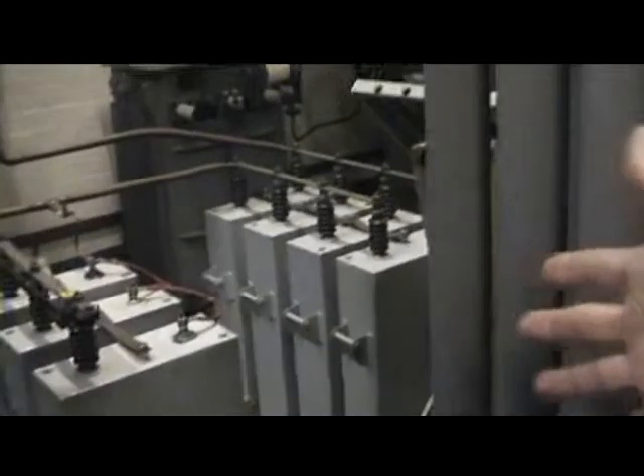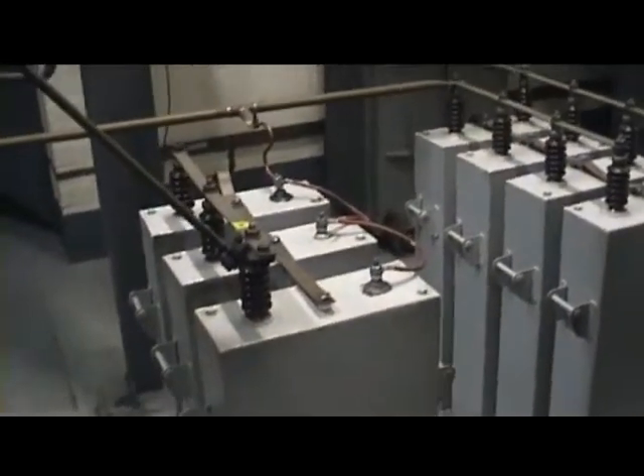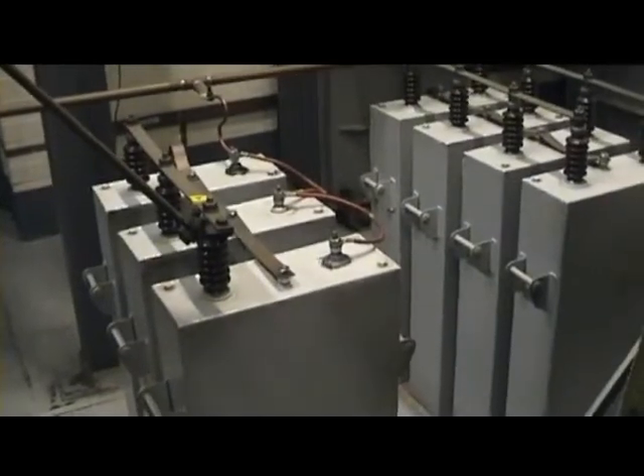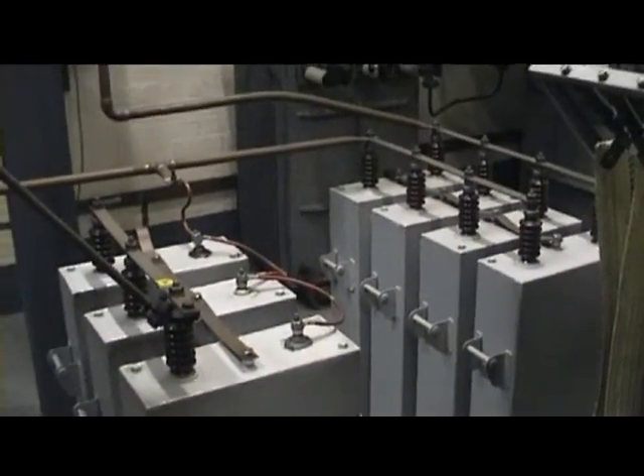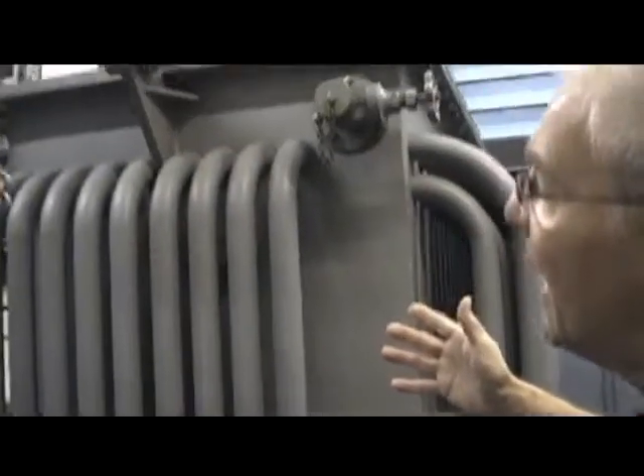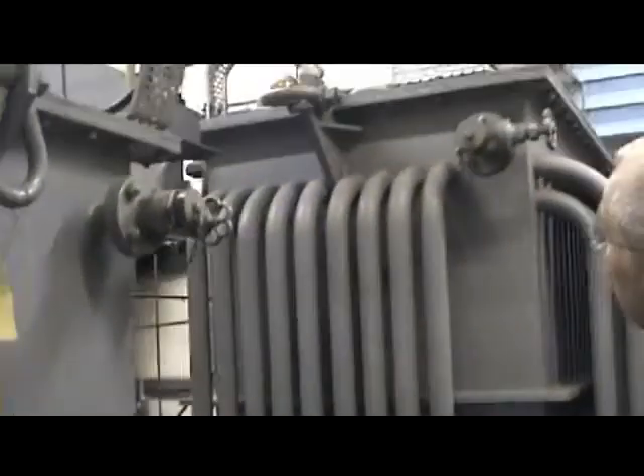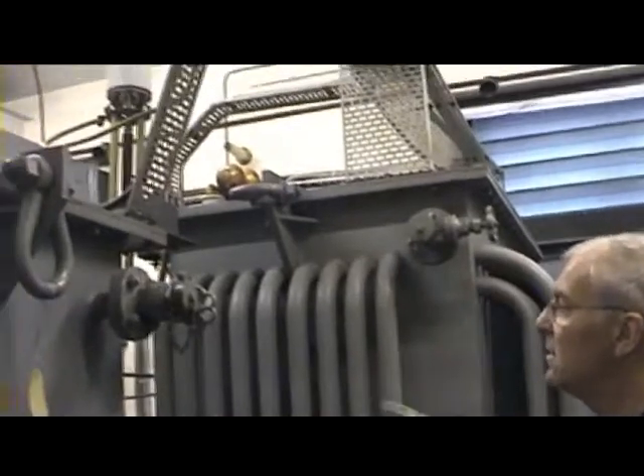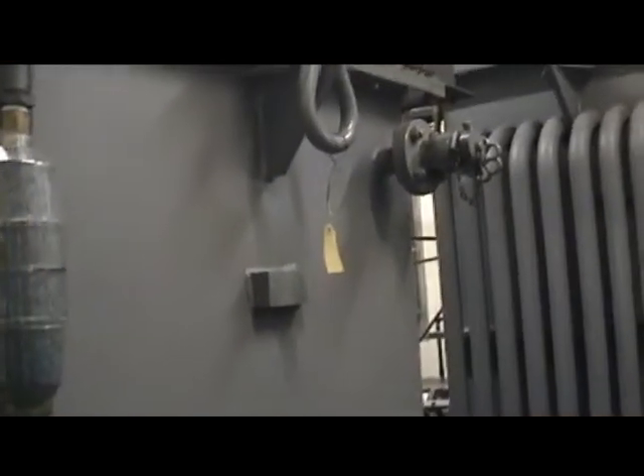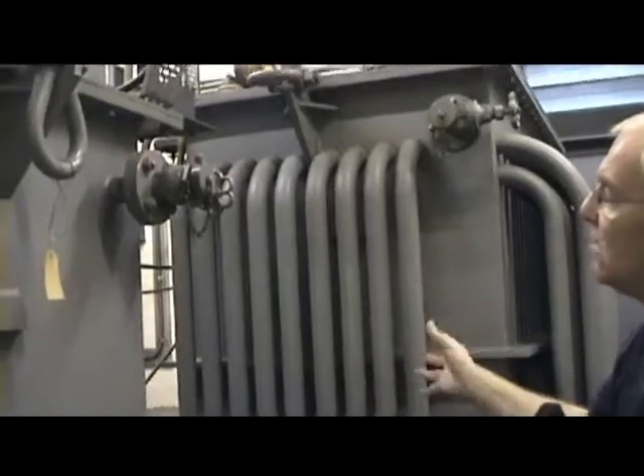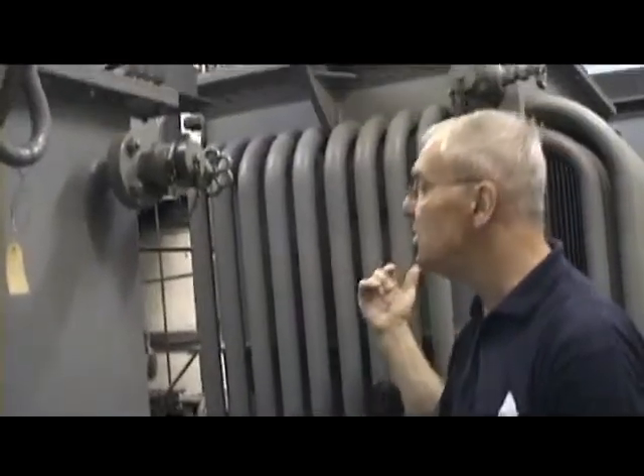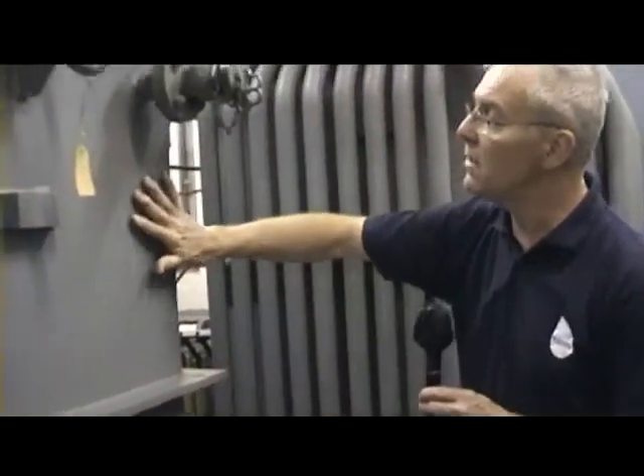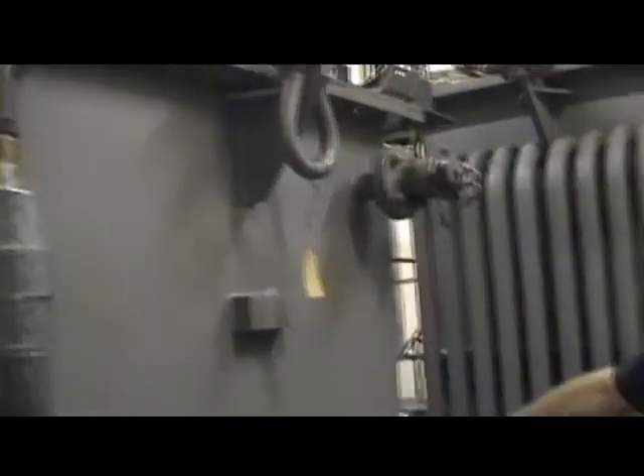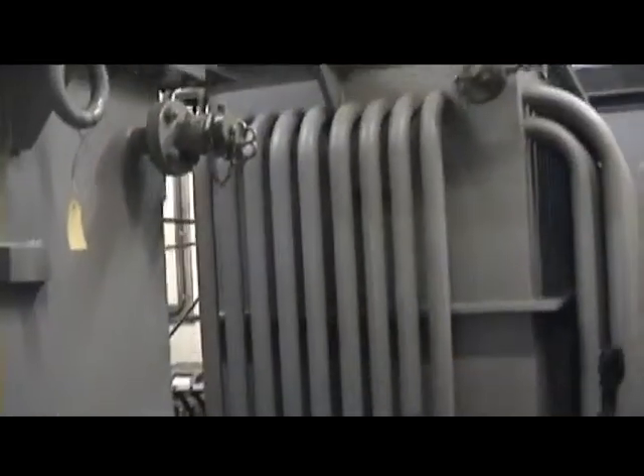Just looking through here, we can see three large capacitors on the floor, a set of three. These are modulation blocking capacitors and are from one connection of the mod transformer to earth. The other connection up to the HT line is made by this reactor, which is here. It's always a reactor in the States, a choke in the UK. This is a low frequency reactor. It allows us to pass the DC through the reactor to the secondary of the mod transformer. The audio power gets superimposed on the DC, which then flows out to the tubes. The DC is prevented from flowing through the modulation transformer secondary by the capacitors on the ground. It's a standard way of doing it.